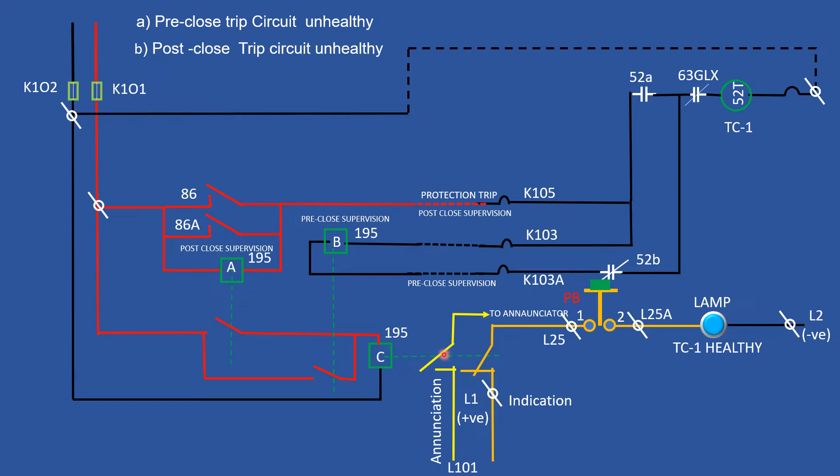We only watch the process of checking unhealthiness of trip coil through indication lamp circuit. Here, the supervision relay is in series with a push button and 195c relay contact. If trip circuit remains healthy, then the indication lamp will glow after pressing push button.